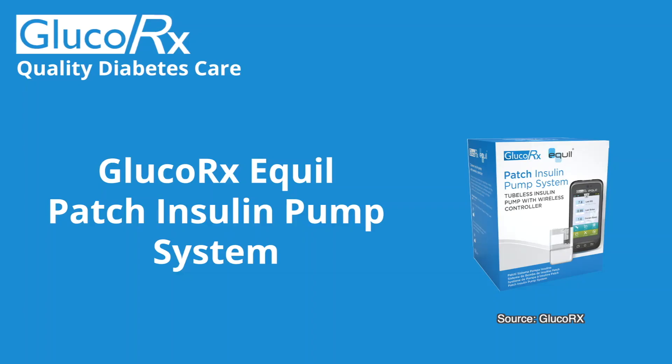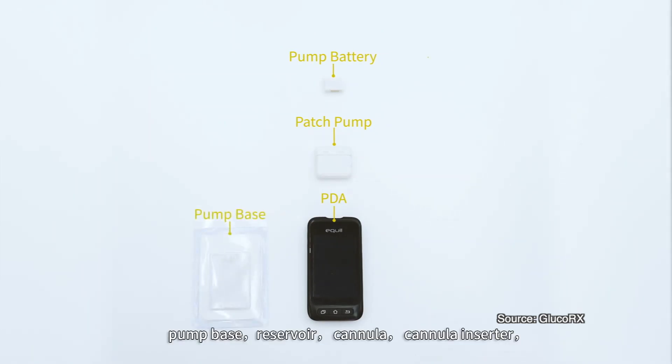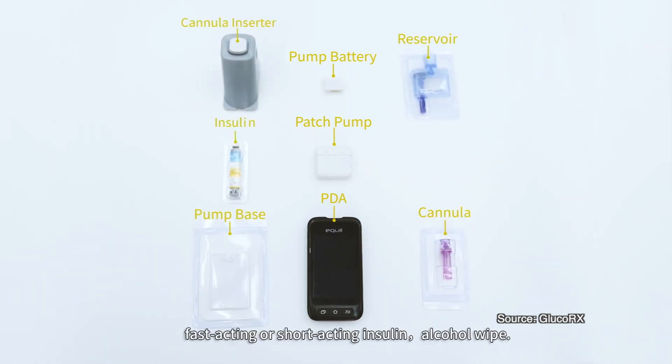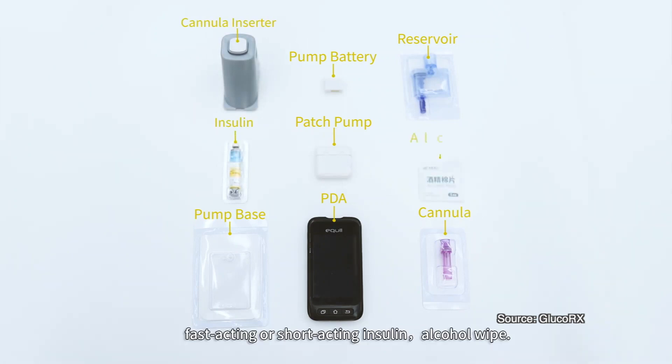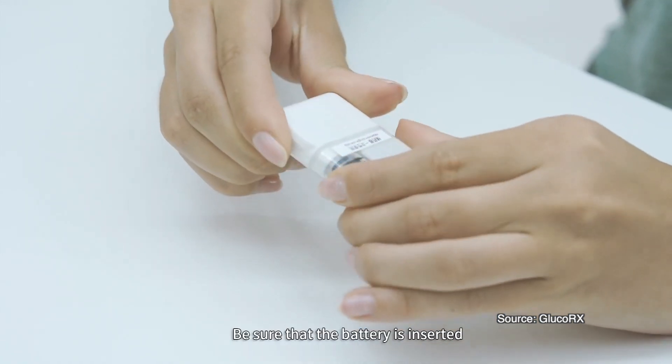As well as announcing a CGM product, GLUCO-RX also announced an insulin pump. Previously they made blood glucose meters, but now they've expanded into the pump space and the CGM space. Their tubeless insulin pump with a Bluetooth controller is called the Equil. This is a patch pump similar to the Accu-Chek Solo — there is a pump base which is changed every couple of days, and a reusable pump patch element with other components like a battery, pump, and reservoir. The pump itself holds 200 units of insulin and is 1.2 centimeters thin.